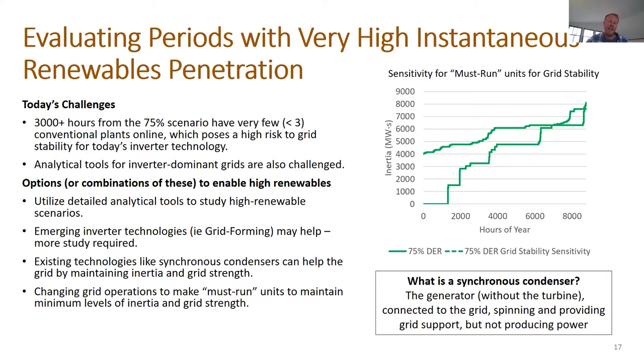And a different flavor of the synchronous condenser approach is changing grid operations to make sure that there's a certain number of must-run units connected to the system, so that you have enough of those grid services from the conventional fleet to support grid operations as we know them today. On that, I'd like to transition over to Ray on the distribution analysis.